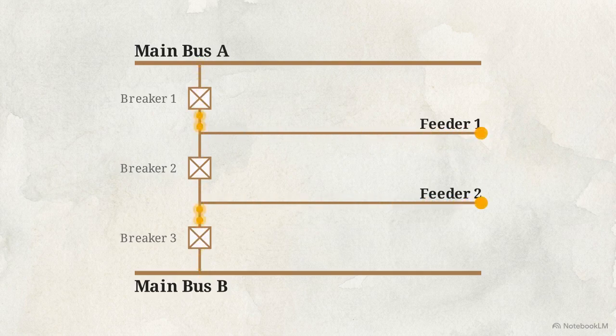But if a severe fault occurs directly on main bus A, the isolation response is highly contained. Only the top row of breakers opens, isolating the failed bus. The operational triumph is clear. Despite losing an entire main bus, both feeder lines remain fully energized from main bus B. This topology solves the core engineering tension. It achieves maximum operational flexibility and fault tolerance without requiring a costly 2-to-1 ratio of complex switchgear.